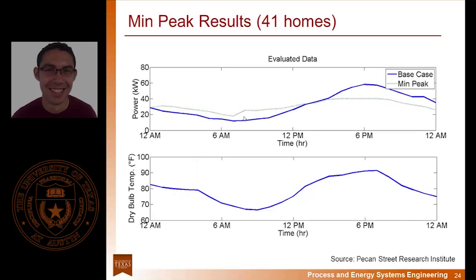The advantage of this centralized controller is that it's able to leverage the passive thermal energy storage of each house by pre-cooling each house on a different operation schedule. That means houses with thinner thermal envelopes or tight thermostat constraints can still run during peak times, while those with large thermal envelopes or comfort bounds can slowly heat up. In both cases, the thermal comfort bounds of each house are not violated, but you're still able to leverage the thermal mass of each home as a community. The decrease in peak is pretty significant.